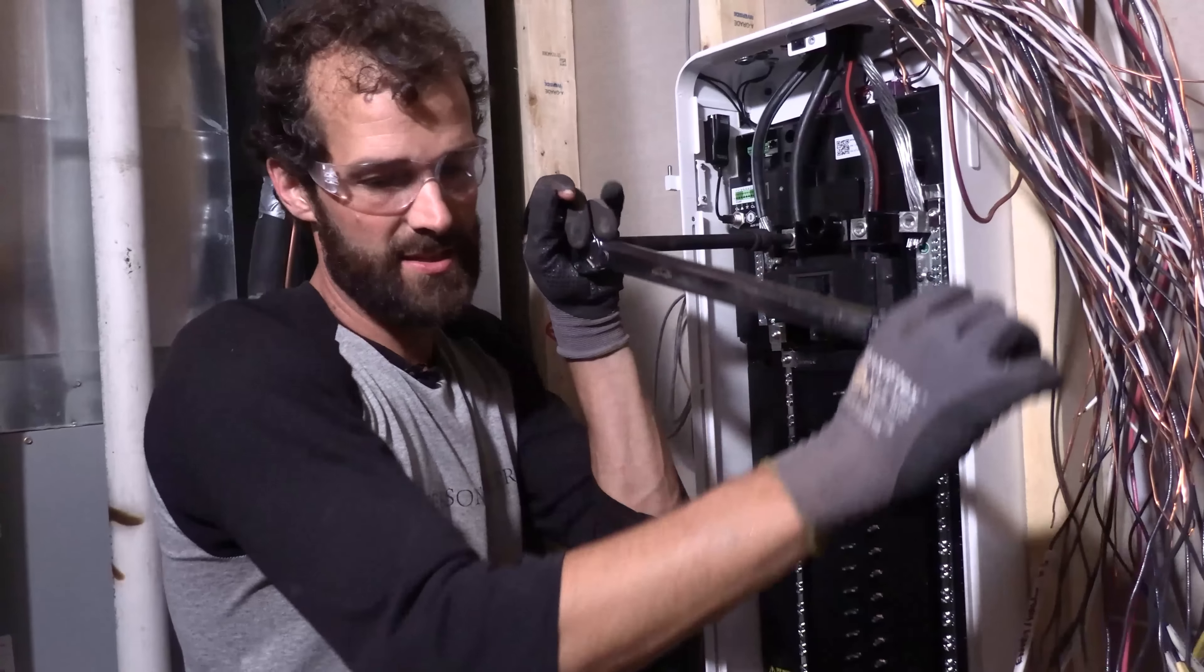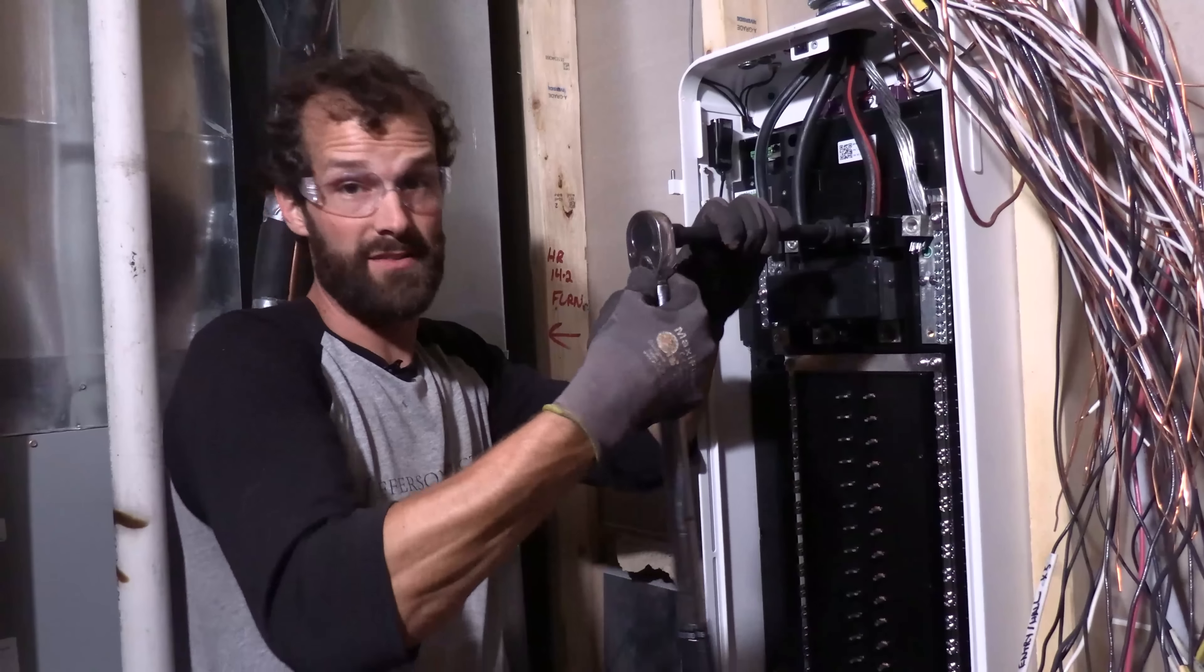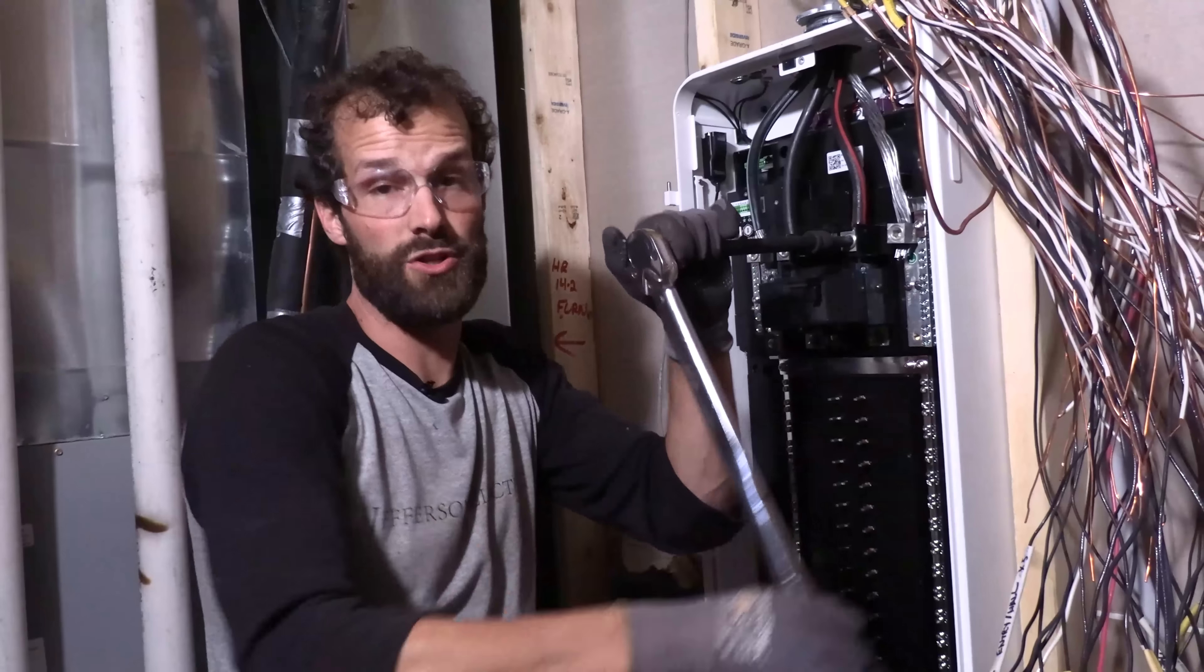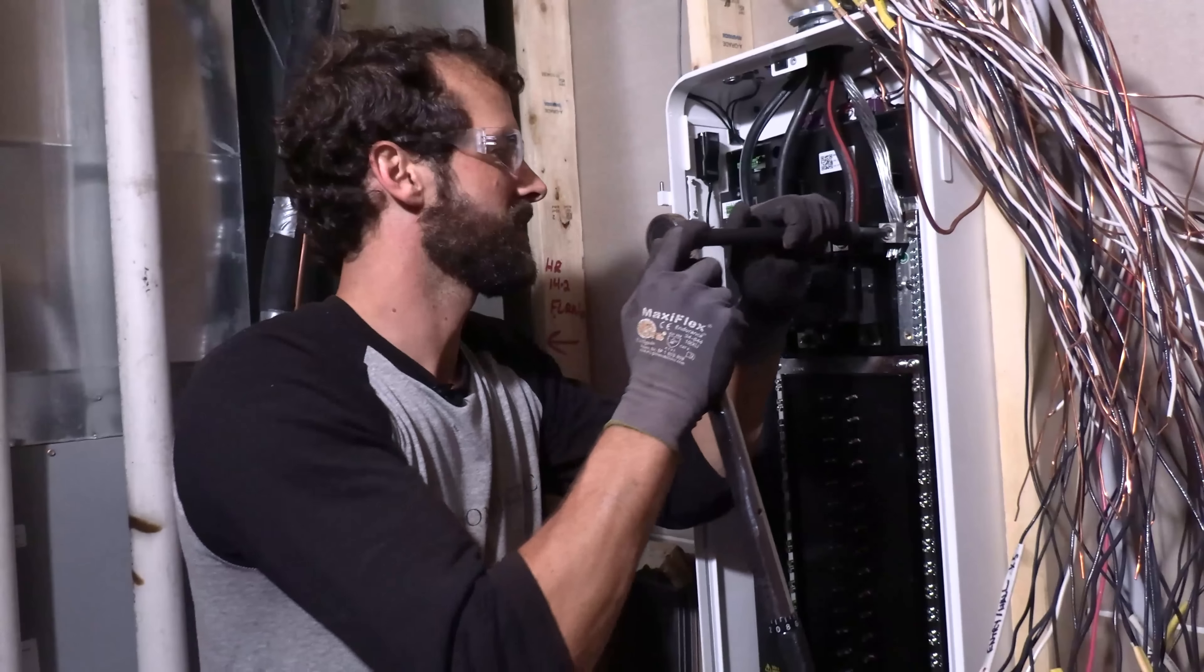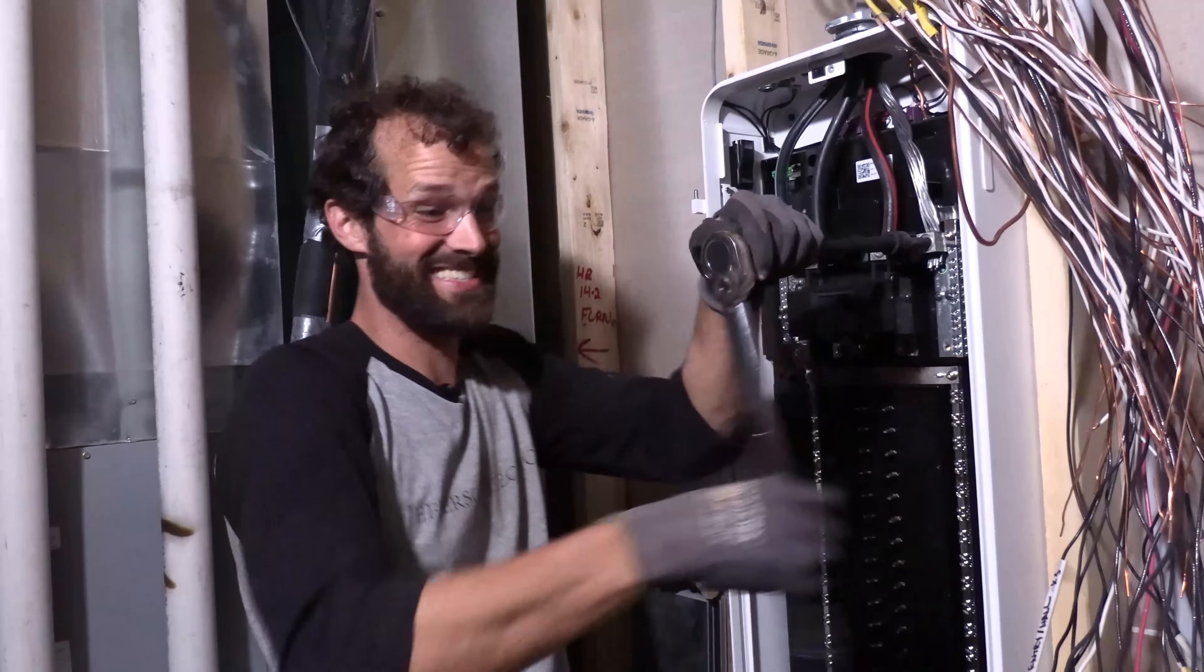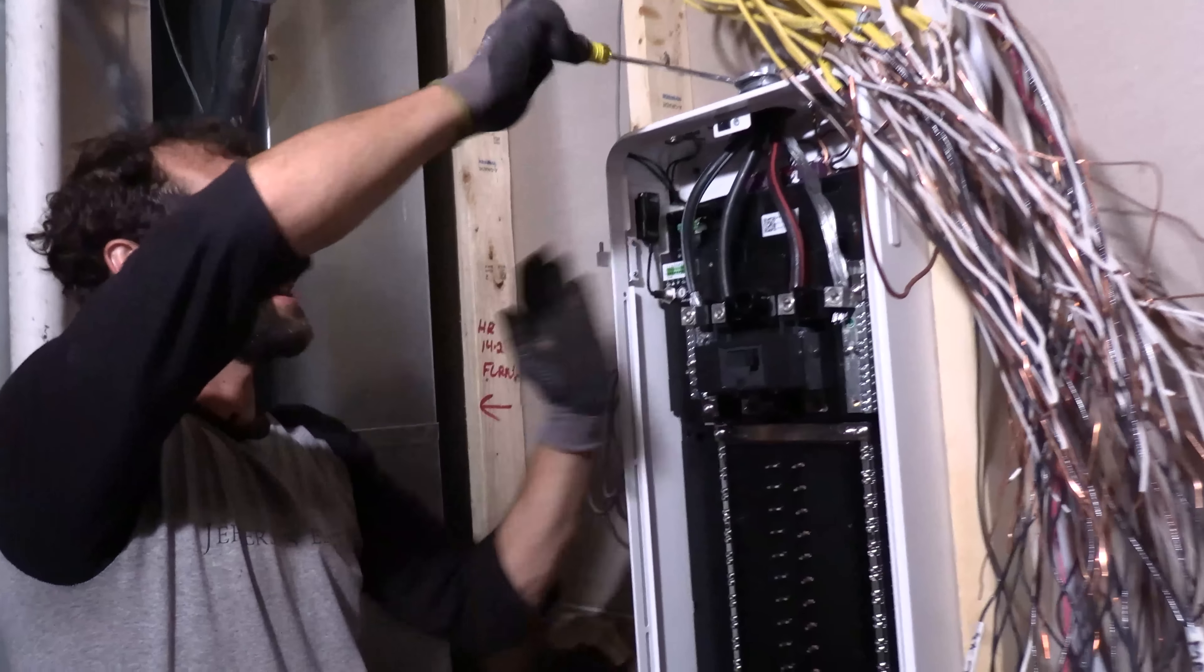With the Tesla system, you've got a Tesla gateway and that's got a bus bar inside of it that you can use to land your inverter outputs. And so you could land some there, some here, and you could get a larger residential system. I think span had one house, East Coast, that has nine of these babies in it. That's real money. Span is made for a 16 on center mounting. It's exactly 14 and a quarter wide. So convenient that they're complying with industry standard there.